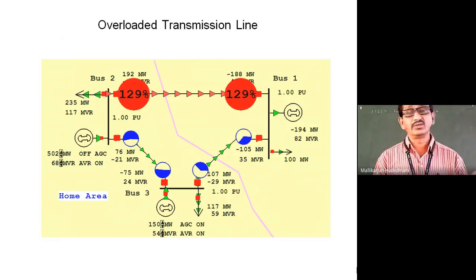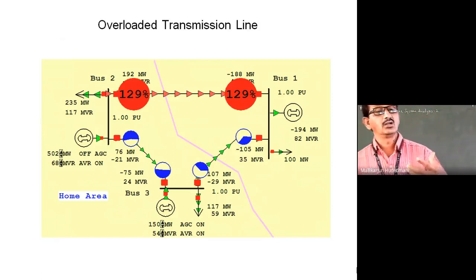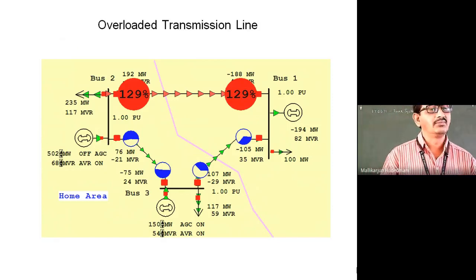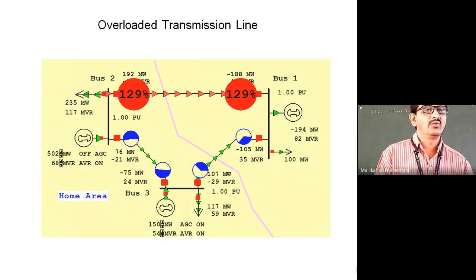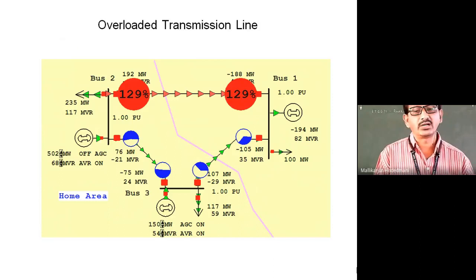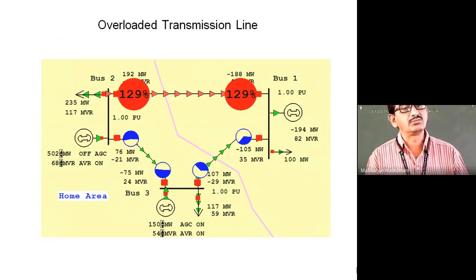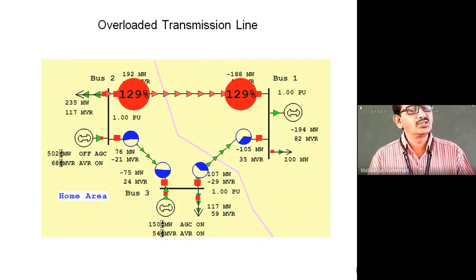The transmission lines find themselves limited because the conducting material put on pole to pole has its own limitations of MVA transfer. The transfer capacity is limited by the conductor's current amperage rating, so they cannot transfer capacity beyond its rating. Therefore this shows a case study: when there is a high power draw from particular loads, even if the generators are capable, the transmission line poses the constraint. They cannot meet the requirement because of transmission ability constraint only.